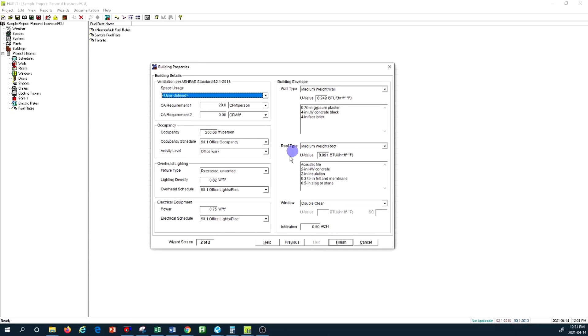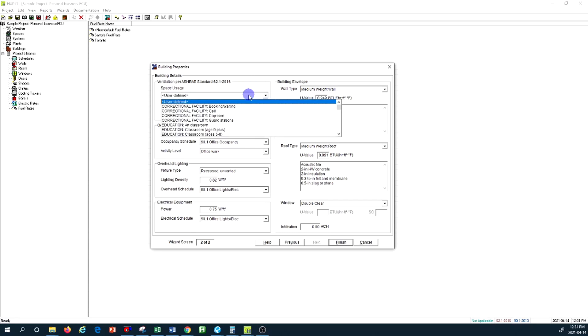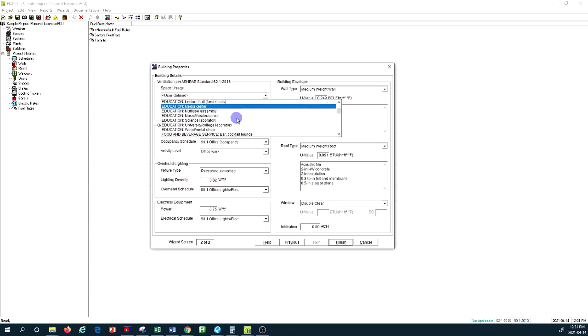Next, okay. Now we have to provide a little bit more information about our ventilation. As you see, the software I am using uses the ASHRAE Standard 62.1-2016 which is the latest ASHRAE standard for minimum ventilation requirement. Basically what we have to do is select the type of occupancy that is for this building.